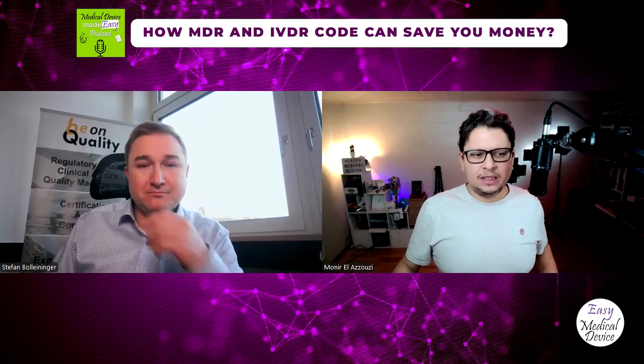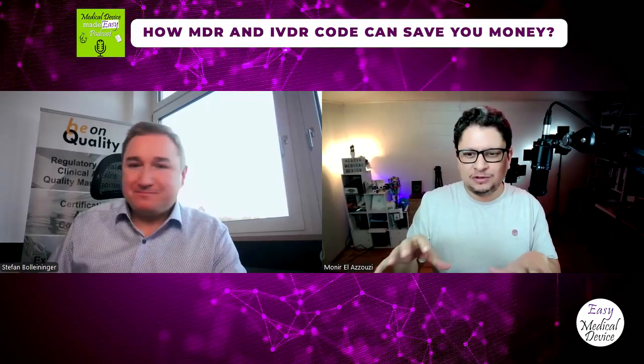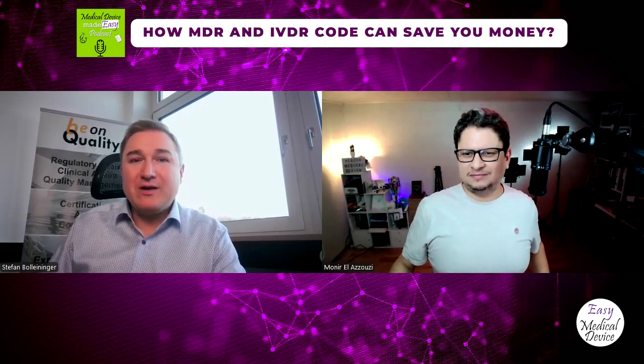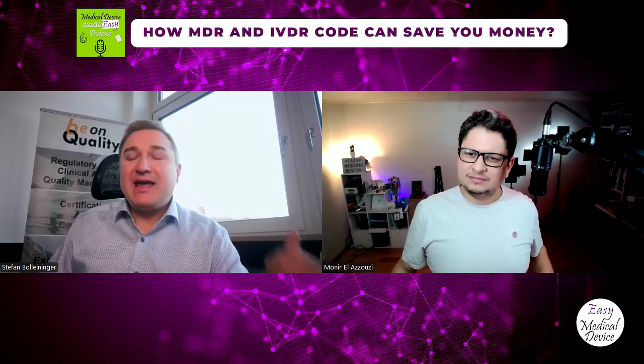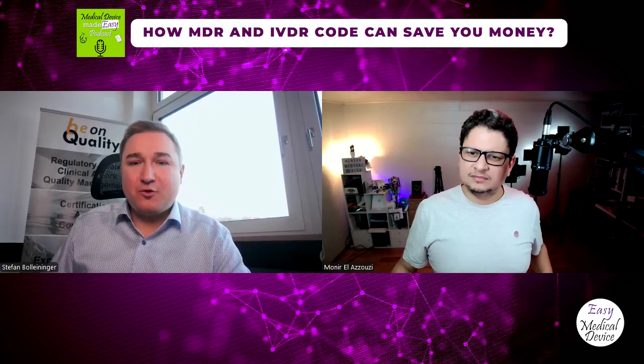Exactly, yeah. So when you said also about the MDS, MDT, IVDT, etc., all those codes that are there, when you say add as many as possible, what do you mean exactly? Can I add codes that I even have not on my product? No. You need to put this. When I say add as much as possible, it is with the lowest effort for your complete product range. You need to have that product. You need to be able to back it up by technical documentation. You need to back it up by products.